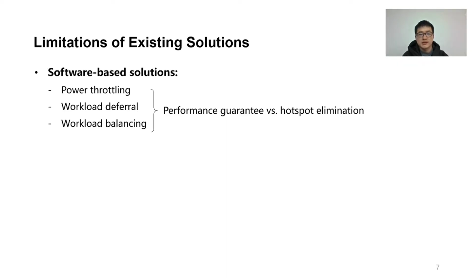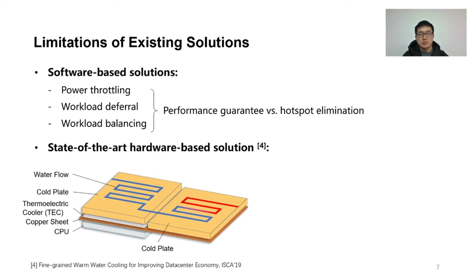Although there are several existing solutions to the hotspot issue in cloud data centers, they have important limitations in edge data centers. For the software-based solutions, it's usually necessary to consider the trade-off between the performance guarantee and hotspot relieving, since end users would place strict demands on performance. For example, some mission-critical edge applications would have no deferrable workloads. Recently, Zhang et al. proposed a hardware-based solution to the hotspot issue for CPU. They integrate each CPU with a thermoelectric cooler to deal with hotspots. They also add a copper sheet and another cold plate to disperse heat when the TEC is turned off.